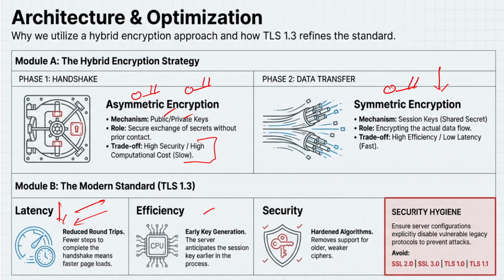Whenever we design the smart grid or the configuration of the SCADA system, right? We should never use SSL. As I mentioned earlier, SSL, that is Secure Socket Layer, is obsolete. So we are not utilizing this connection anymore. What we are using is TLS 1.2, and even TLS 1.0 is not recommended. It is always 1.2 or else 1.3 version of TLS.